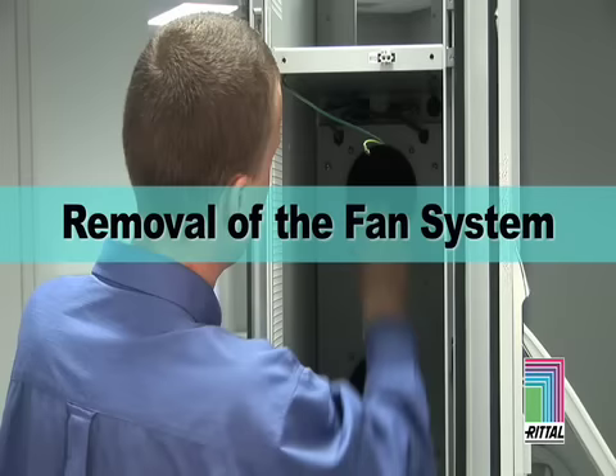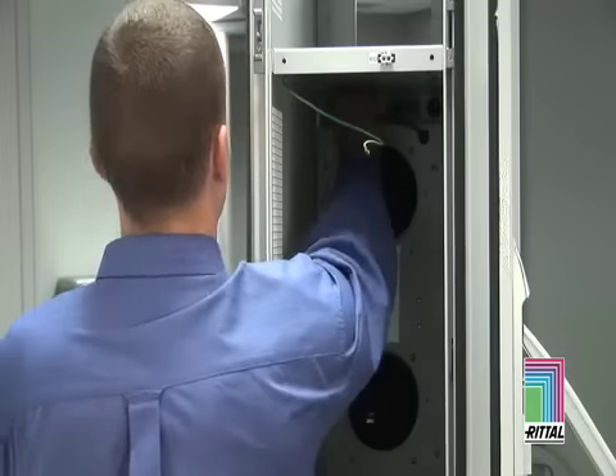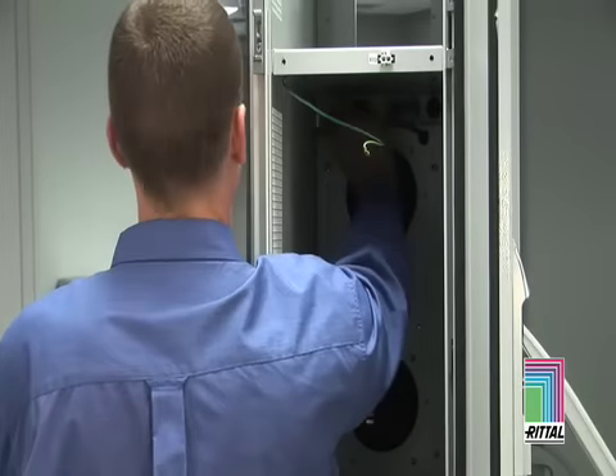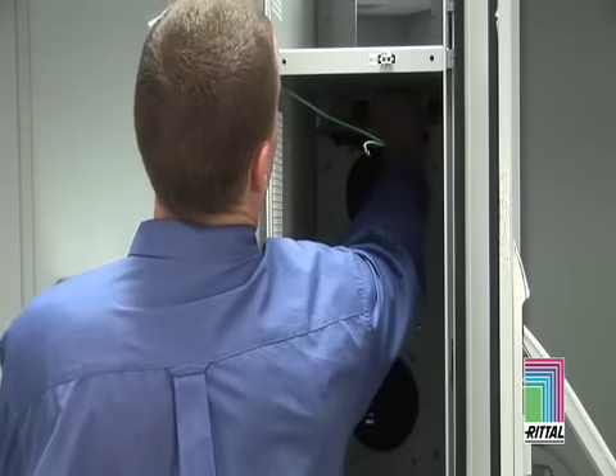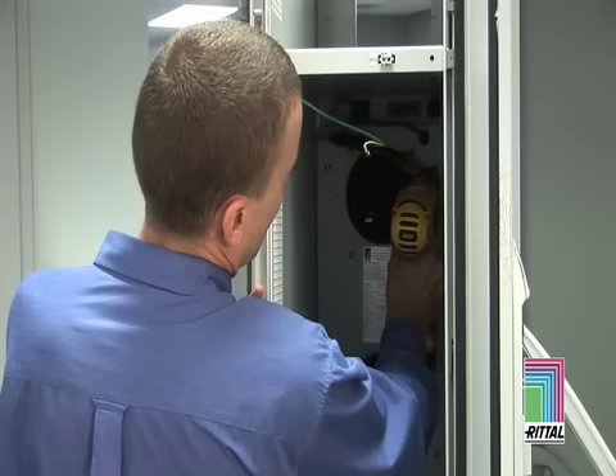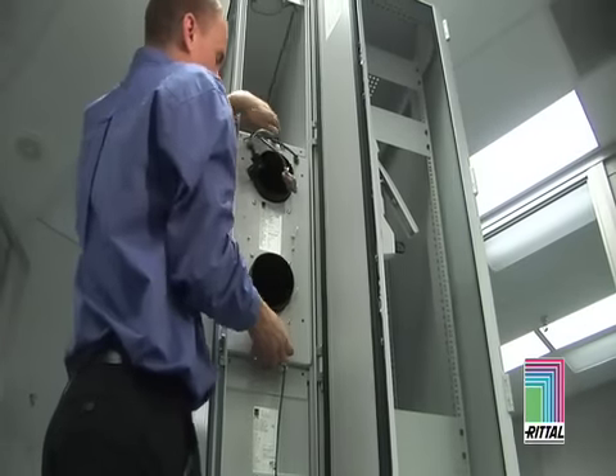Removal of the fan system. Removal of the fans is accomplished by first disconnecting power from the fan modules, then disconnecting the communications cable. Removal of the 4 screws holding the fans in place will allow complete removal of the fan pair.